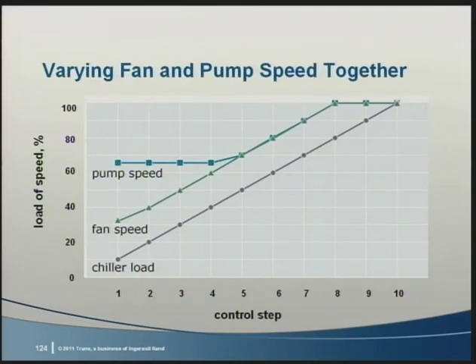Once the pump reaches its minimum speed, maintain its drive at that speed and allow the cooling tower fan speed to continue to decline. On this job, the condenser pump minimum is 67% and is set by the need to produce the static lift from the basin to the top of the cooling tower.